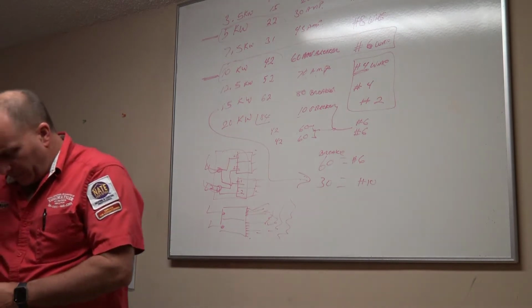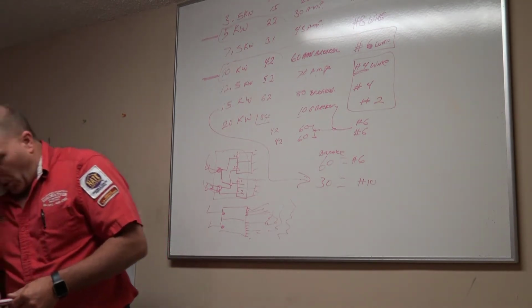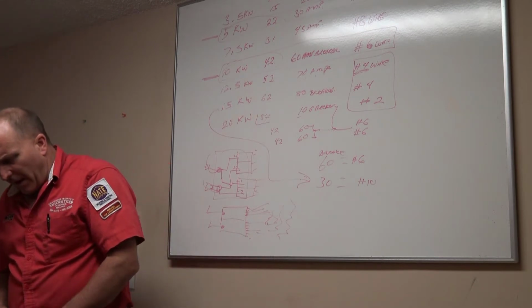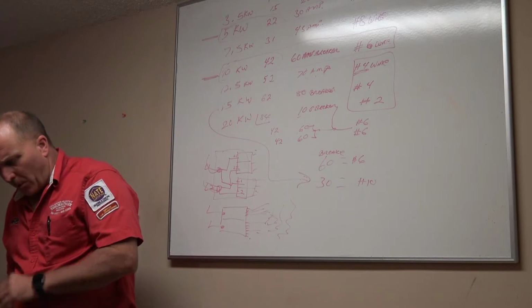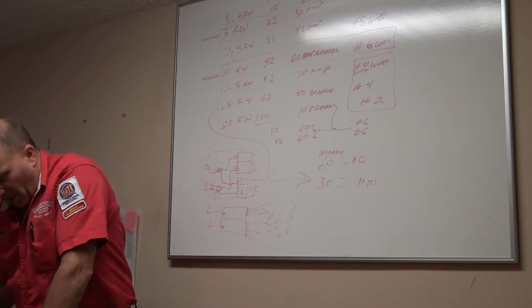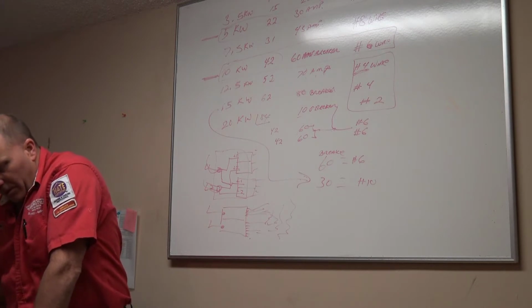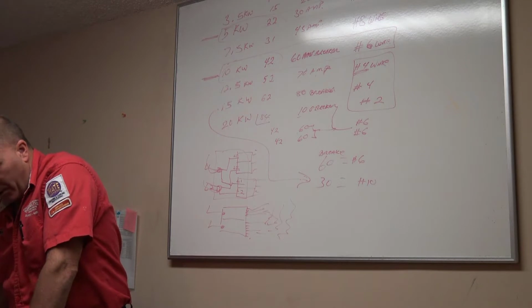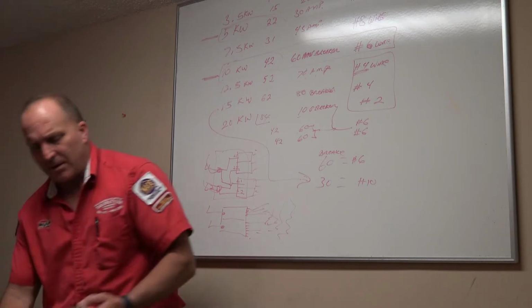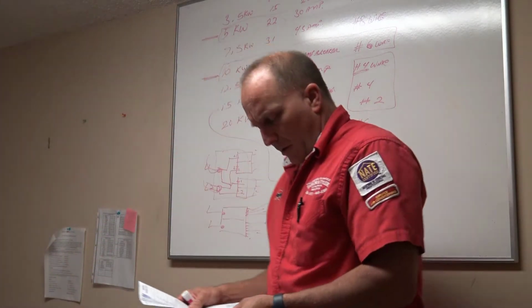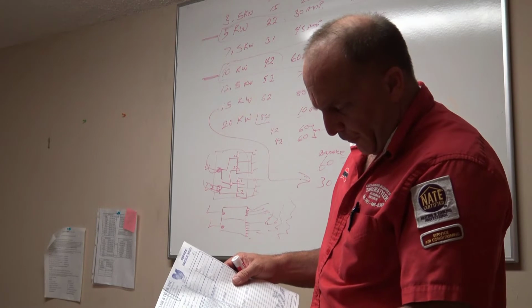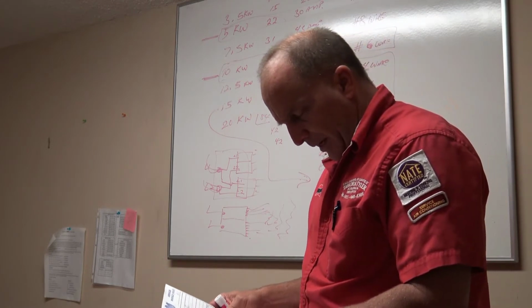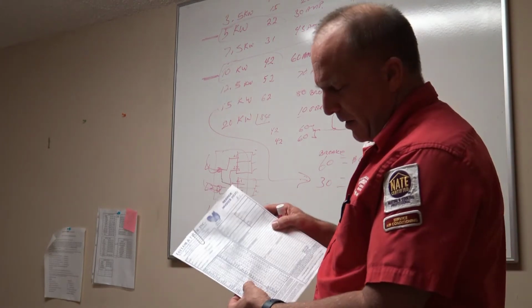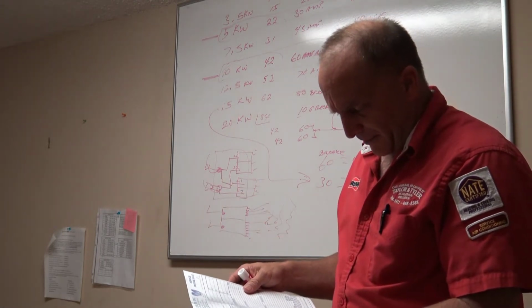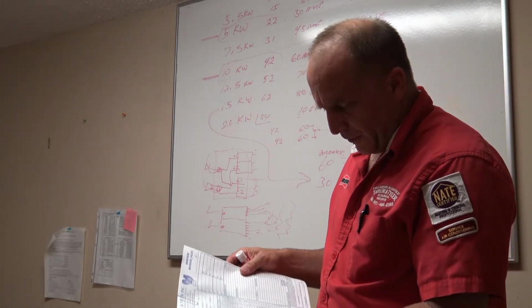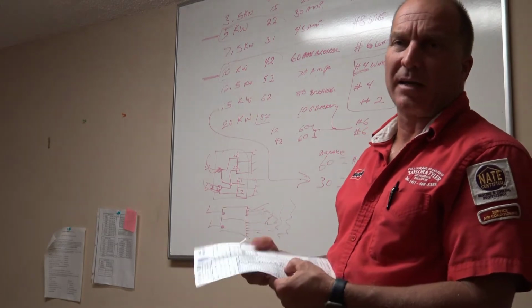Amperage draw total is number 5. This is the total amperage of all heating elements. The amperage draw is approximate and includes the blower motor running as well. If it is a couple amps off, it's okay. So 42 means your total amps is 42. On my checklist here, I've got amperage draw and I have 42, 64, and 85 on here already, okay? And then above it, I have 10 kW heat, I'm sorry, 15 kW heat, and 20 kW heat, because that is most of the time what we run across.